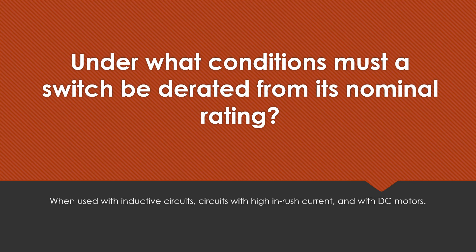Under what conditions must a switch be derated from its nominal rating? When used with inductive circuits, circuits with high inrush current, and with DC motors.